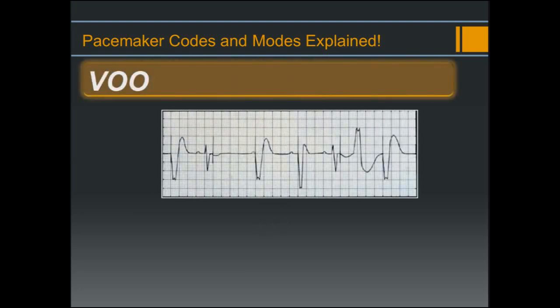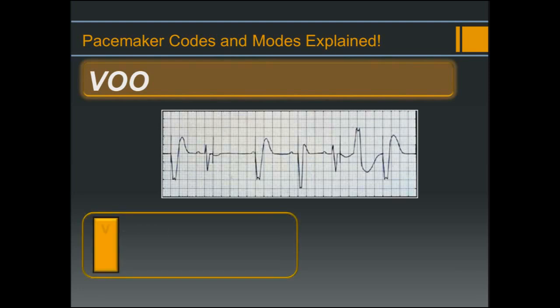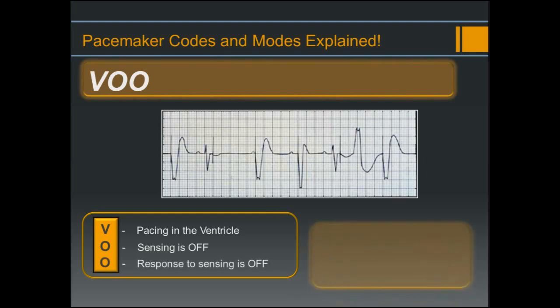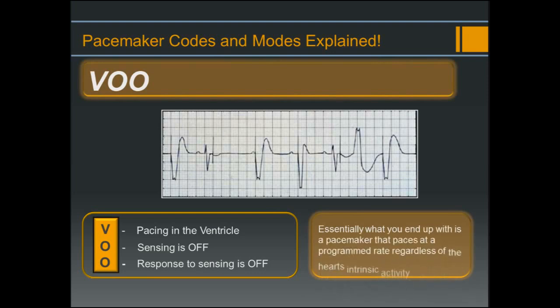First up is VOO. Breaking down the code letter by letter: pacing is in the ventricle, sensing is off, and a response to sensing is off as well. Essentially, what you end up with is a pacemaker that paces at the programmed rate regardless of the heart's intrinsic activity — also known as asynchronous pacing.